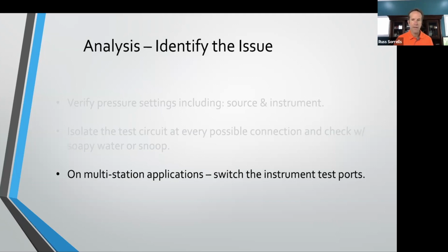Multi-station applications. We talked a little bit about this last week. Just take the test lines out of the instruments and swap them. That allows you to identify, does the issue stay with the instrument, or does the issue stay with the fixturing? So that's if you have a multi-station application, or if you have multiple applications that may be manual, you can still make that change to identify where the issue resides. Is it in the instrument, or is it in the actual fixturing and tooling?